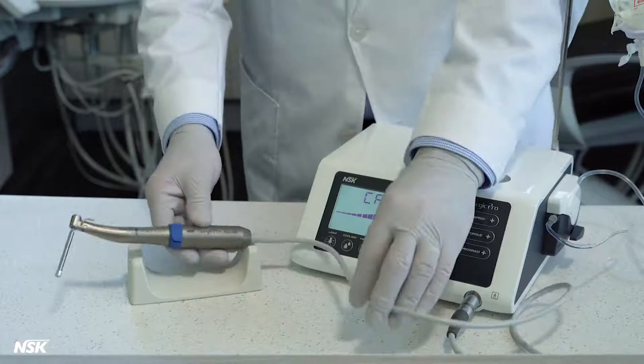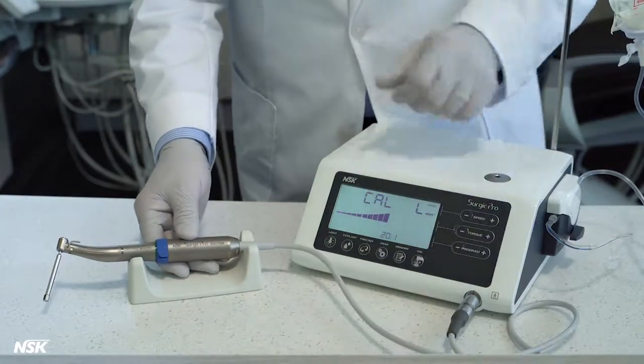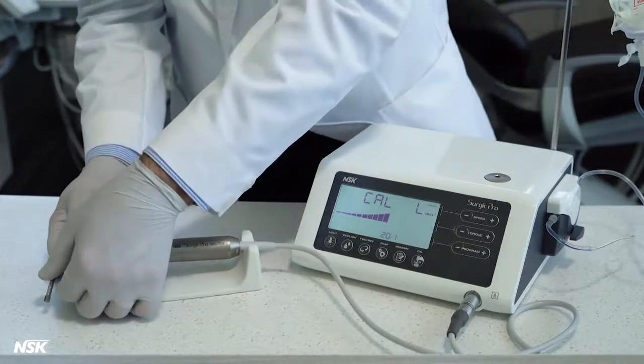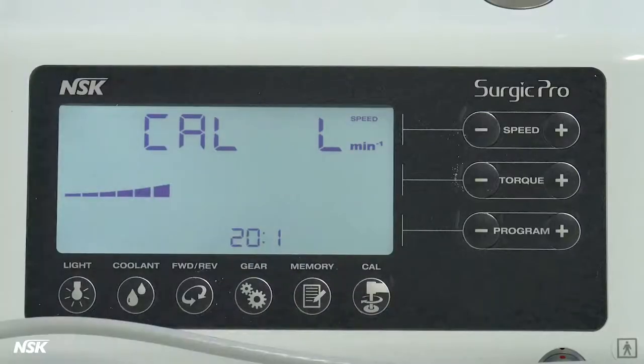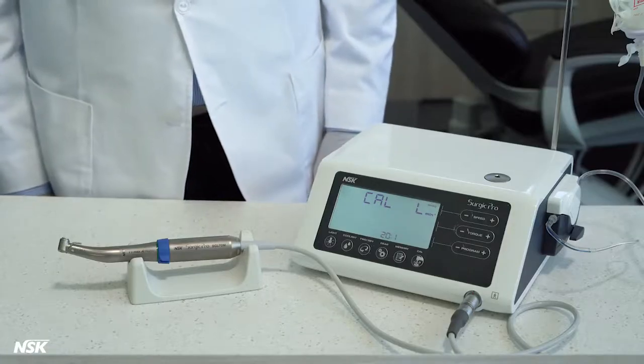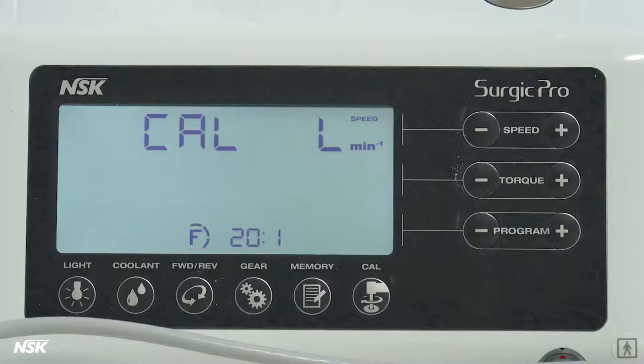Step three, speed calibration. Remove the drill and leave the motor and the attachment on the handpiece stand. Press the cal key. The attachment will start working and rotate for eight seconds at slow speed and another eight seconds at fast speed. When it's done, you will hear a beep and the calibration process is complete.